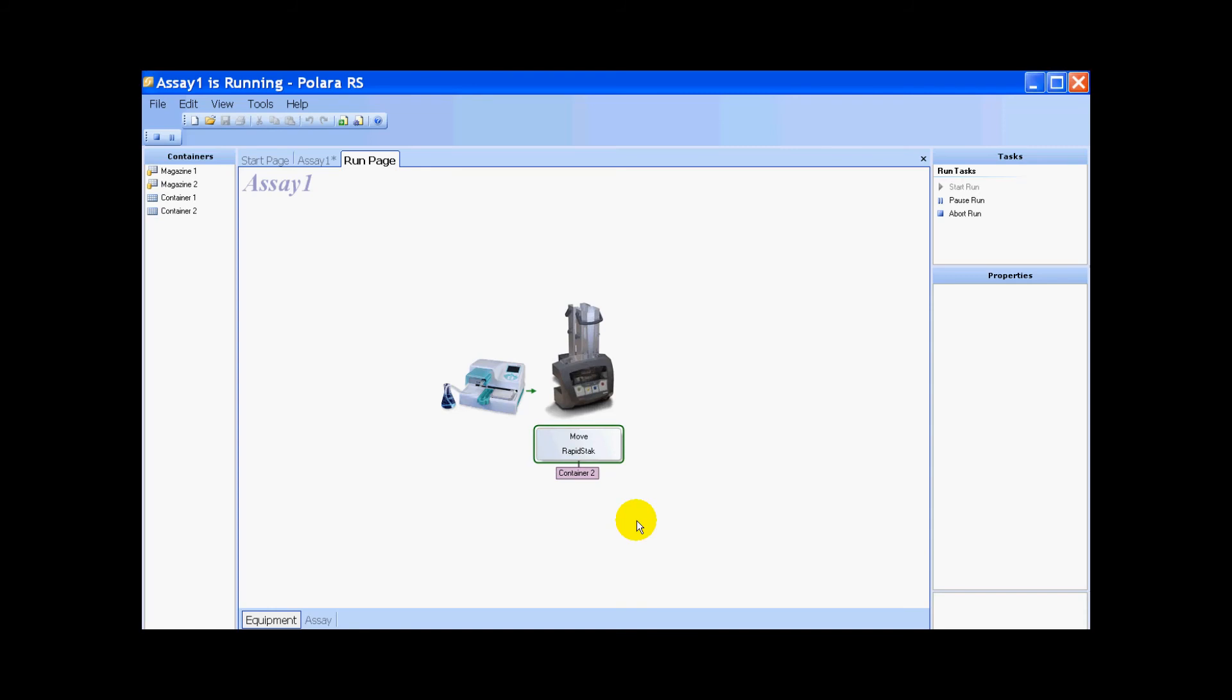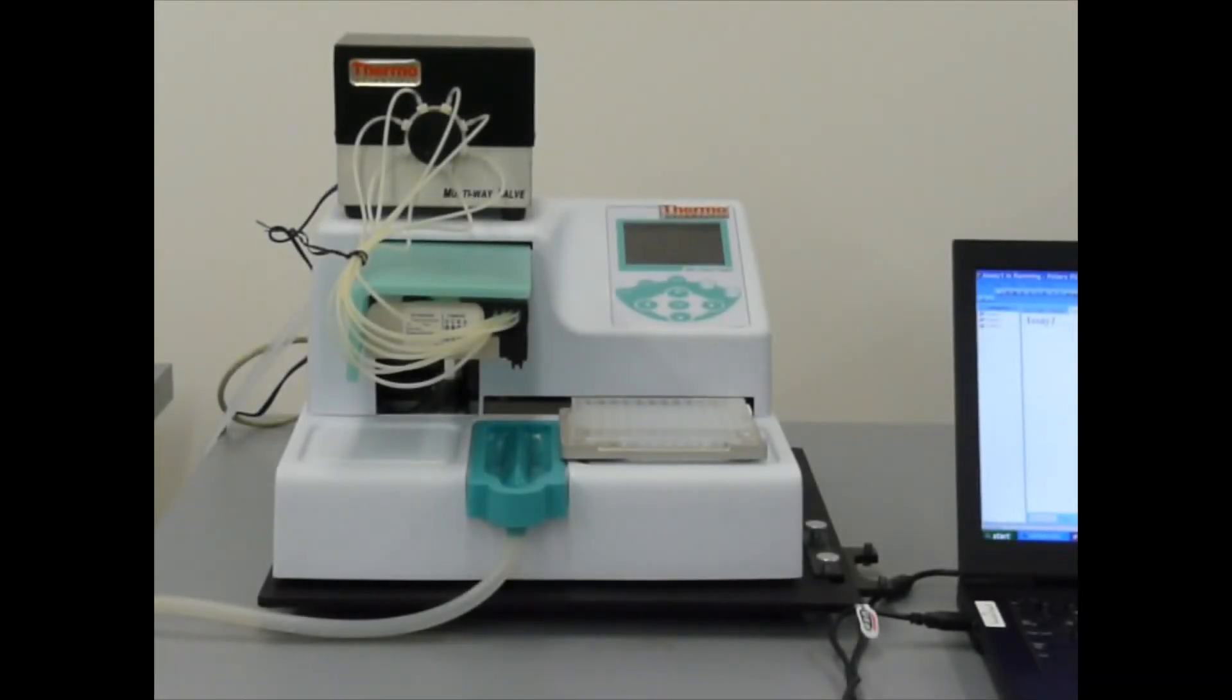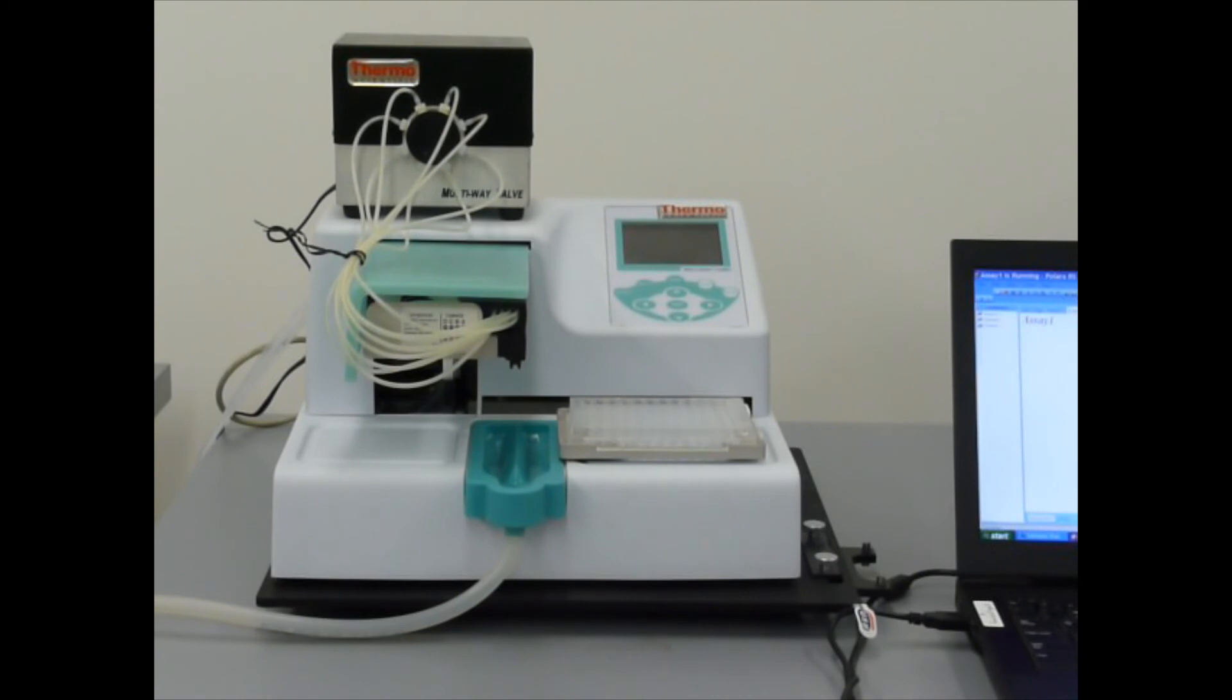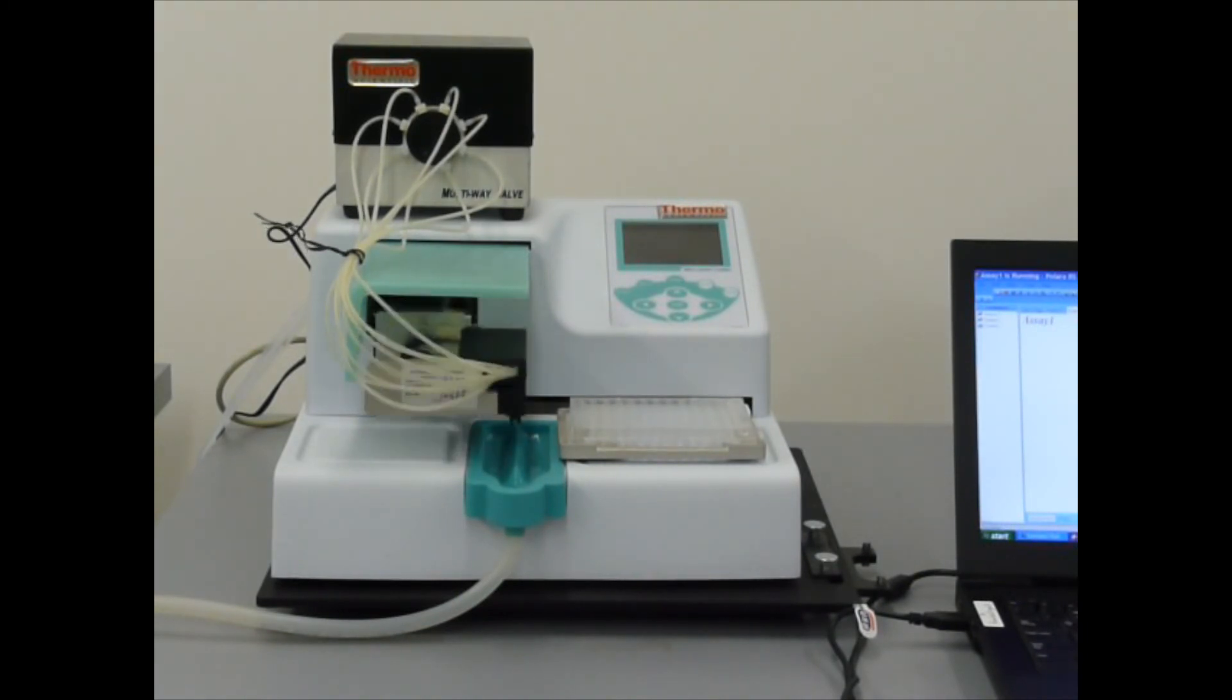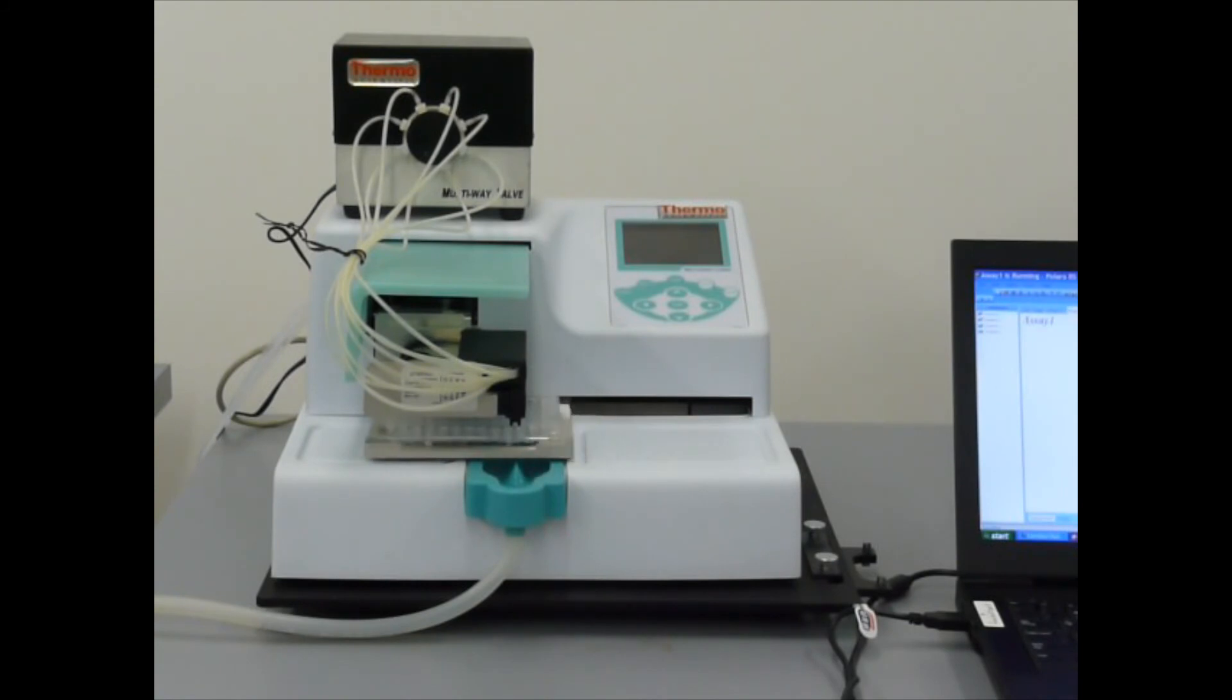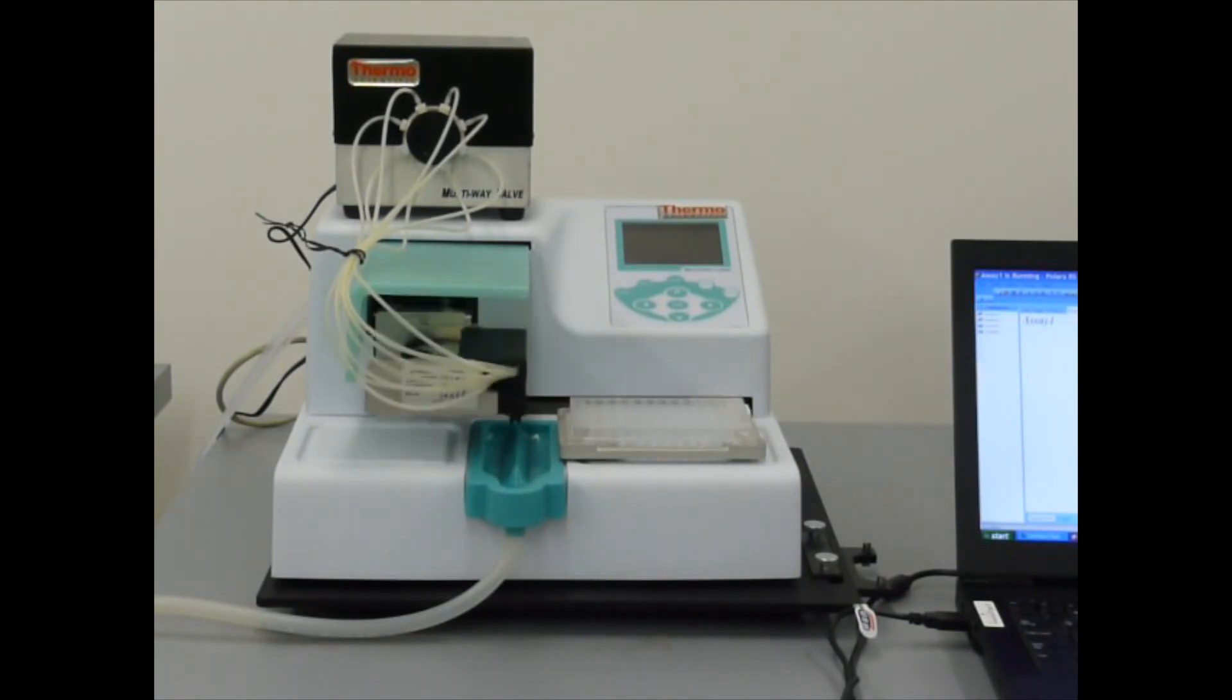Let's see what this looks like on the actual system. Here we are in a live view with the combi and the valve hooked up, and you can see the laptop over to the right. I just have a clear plate sitting on the combi nest and I've selected run this assay. It's priming reagent one, going to run the first reagent. There we see it's priming now with water.